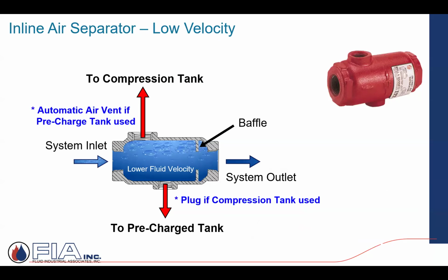So the first one up is based on velocity, a simple little air scoop, or air separator is the term you'll see out in the industry. The way it works is the diameter of the piping, right? There's a certain velocity, feet per second. How fast does that water move? There's an engineering standard, and it's very accepted, typically 4.5, maybe 5 feet per second. This simple little device is engineered diameter-wise relative to the pipe size it's attached to, so that flow goes from 4.5 or 5 feet per second to a half a foot, 6 inches per second, I should say. So it's just a wide spot in the river.